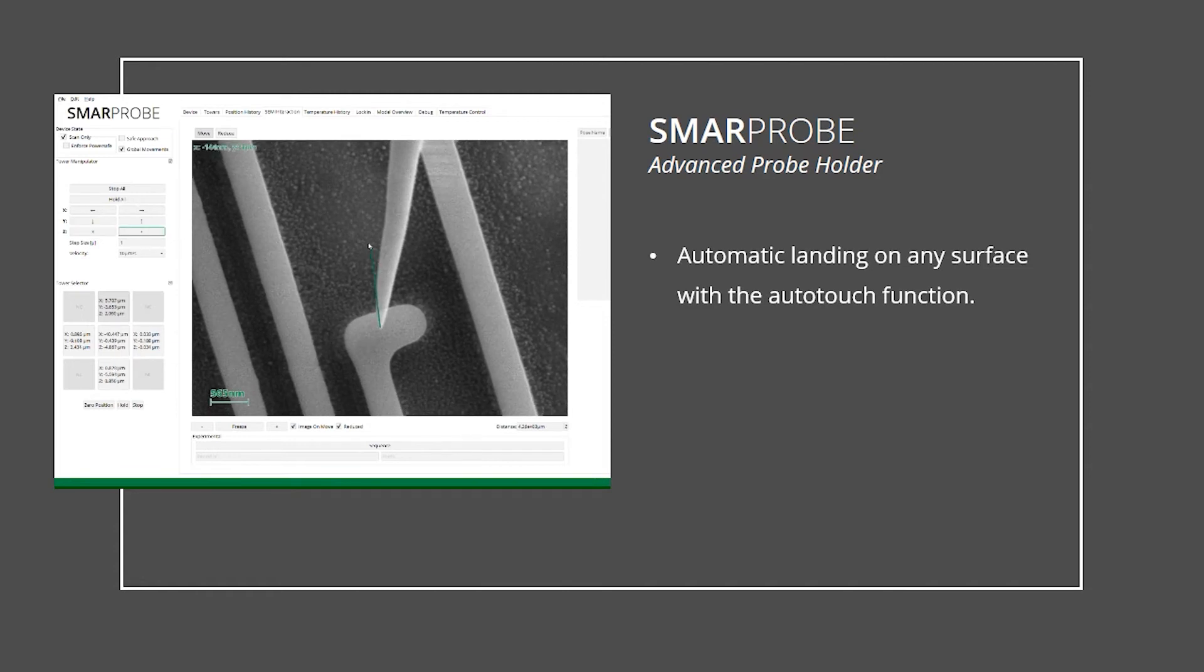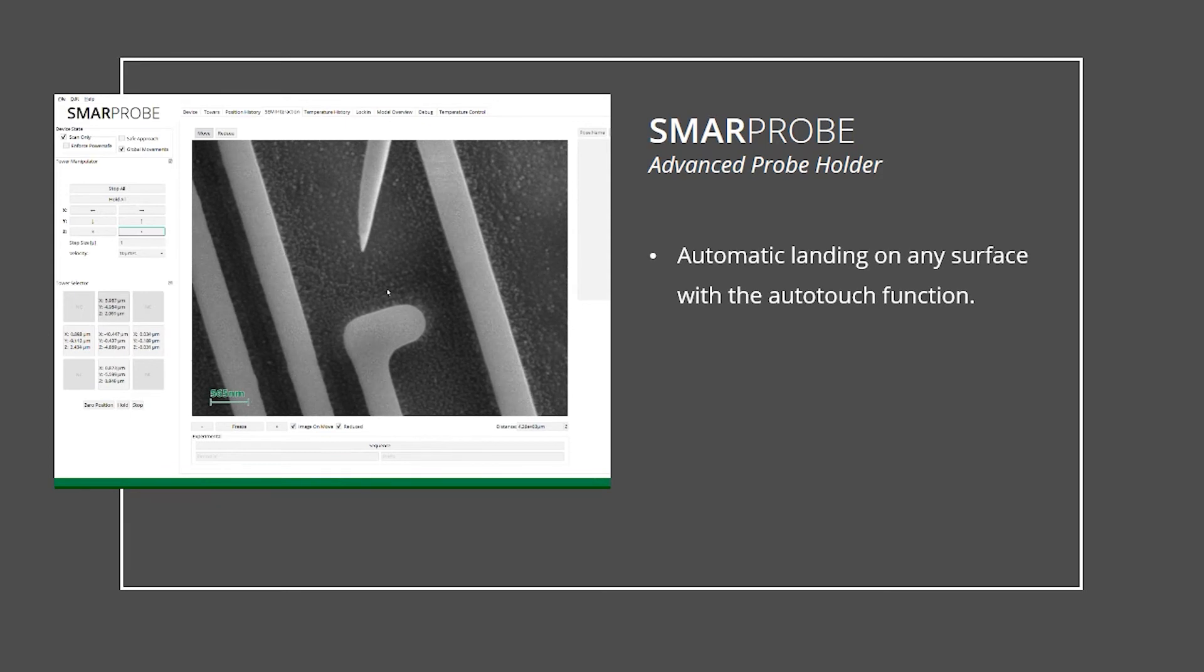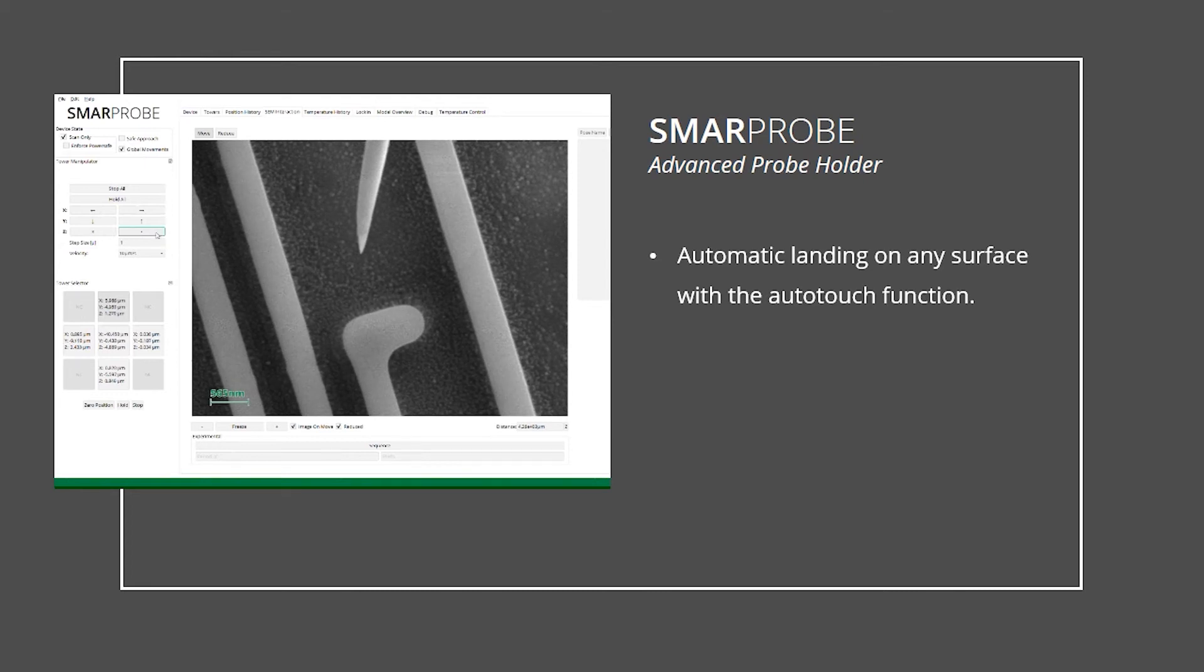After lifting the probe, it automatically lands on the silicon oxide layer without any damage. From here, you can use the probe holder to take AFM images of the sample topography.